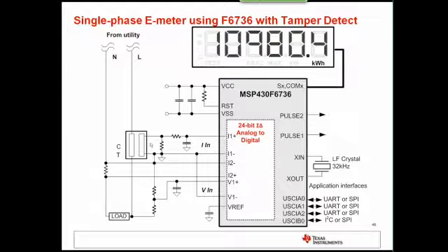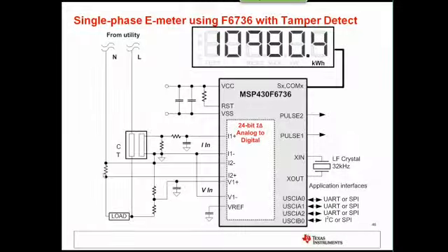All right, this shows a single-phase E-meter using the F6736 with tamper detection. You have the CTs as the current sensor on the line channel, and you have the shunts as the current sensor on the neutral wire. Based off of whether there's a high deviation between these two types of currents, this can indicate if the meter has been tampered with. And you also see the voltage divider, this part of the diagram, and then there are also the anti-aliasing filters.